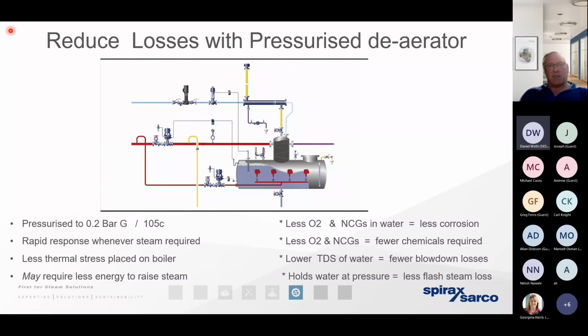But because the pressurized deaerator is pressurized to 0.2 bar gauge, this is an excellent place for us to recover all of that flash steam that was previously being vented away and lost. So it means we can now move very, very close towards a zero net loss steam distribution system.